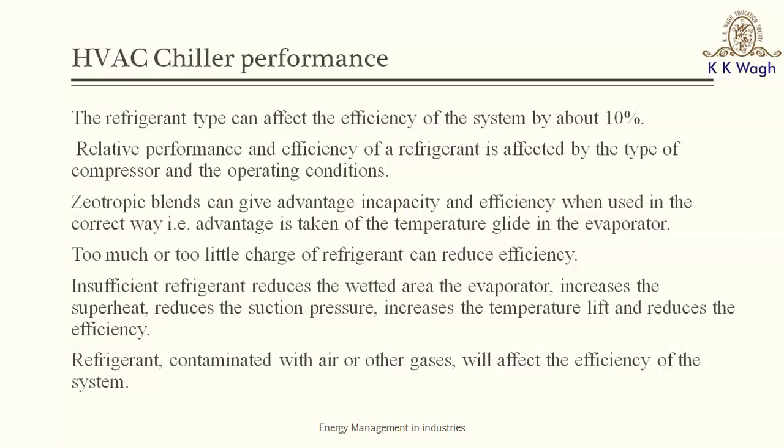There should be no gas entry or air entry into the refrigerant, because that would eat away the performance of the system. The entry of gas and air, which have poor heat transfer characteristics, would unnecessarily occupy the space, that is, the evaporator space, and impact the coefficient of performance of the system. So these are factors we need to keep in mind when we talk about chillers.